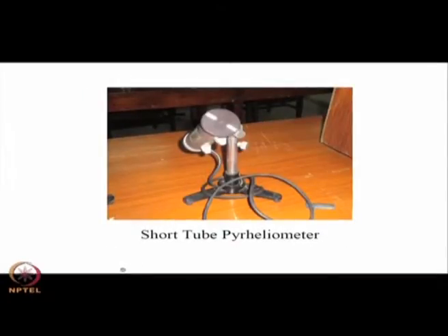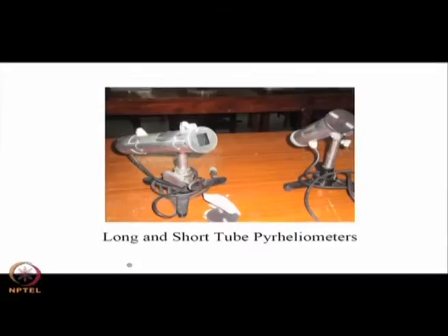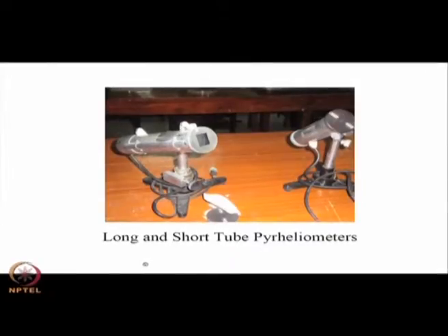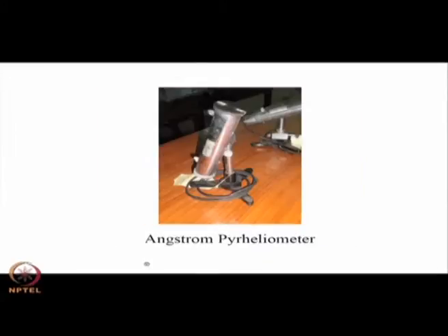This is a short-tube pyrheliometer. At the bottom of that long tube there is a sensor which gets heated by solar radiation. When the cap is removed, it is directed towards the sun and the rays falling on the sensor heat it. The difference between the long and short tube pyrheliometers is that the long one, when uncovered, has a lesser subtended angle and measures radiation emanating from the sun only, while the short tube one has a higher subtended angle and measures radiation also coming from around and surrounding the sun.